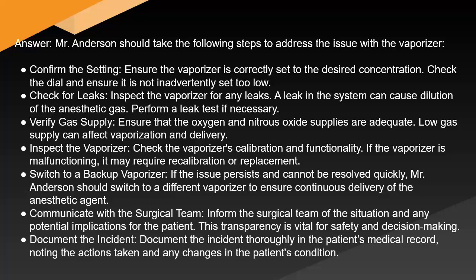Confirm the setting. Ensure the vaporizer is correctly set to the desired concentration. Check the dial and ensure it is not inadvertently set too low. Check for leaks. Inspect the vaporizer for any leaks. A leak in the system can cause dilution of the anesthetic gas. Perform a leak test if necessary. Verify gas supply. Ensure that the oxygen and nitrous oxide supplies are adequate. Low gas supply can affect vaporization and delivery.